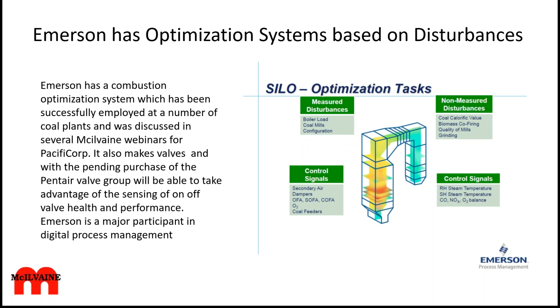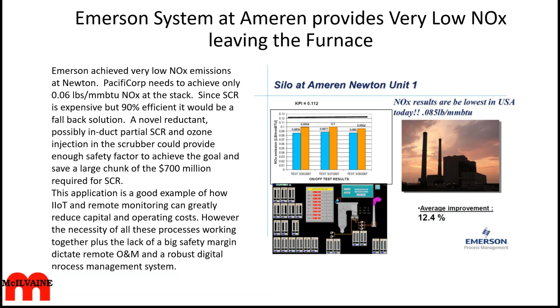The Emerson system at Ameren actually gets down to 0.085 pounds per million BTU within the boiler itself. If you can do that, it's possible to go the rest of the way without a full-scale SCR system. That was part of what PacifiCorp was pursuing in our webinars. Uncovered was the opportunity to do that with things like ozone injection into the scrubber, which is being seriously considered right now. So it does seem to be an intriguing opportunity, particularly in India, where right now you have a large number of old boilers for which NOx control, particulate, and SO2 has to be applied. In fact, there's over 100,000 megawatts of boilers in India that will be candidates for all this.